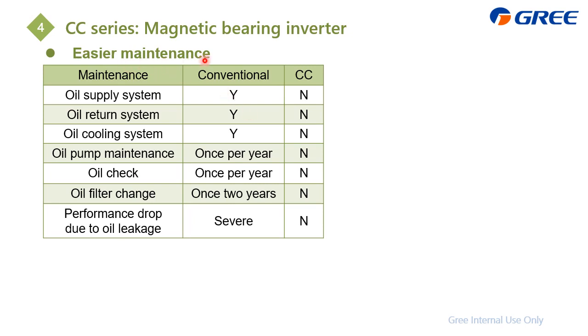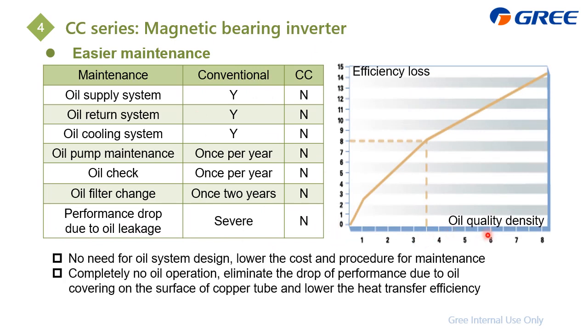For the maintenance, just compare with the conventional one, which is the CE or the CVE series. First we need to replace the oil, including the oil supply, oil return, and oil cooling. Then we check the oil pump and the oil quality, and also replace the oil filter. And if there is a performance drop, it is always due to oil leakage. For this one, we can also save it. And here is the oil quality degradation. That means as the system operates, the oil will deteriorate. Instead, for CC, there's no oil, so we can eliminate this potential problem.